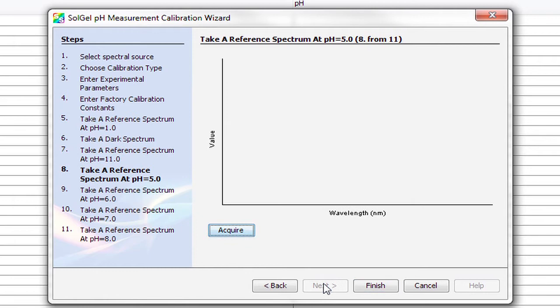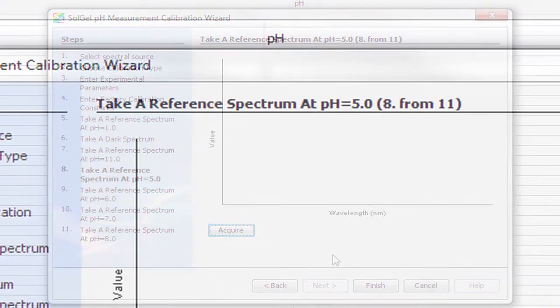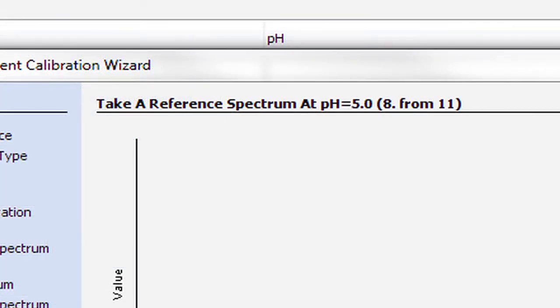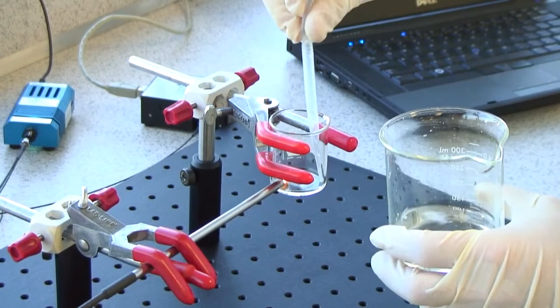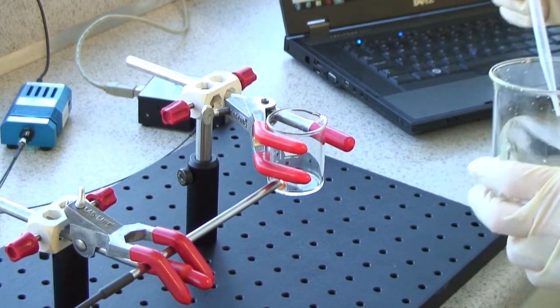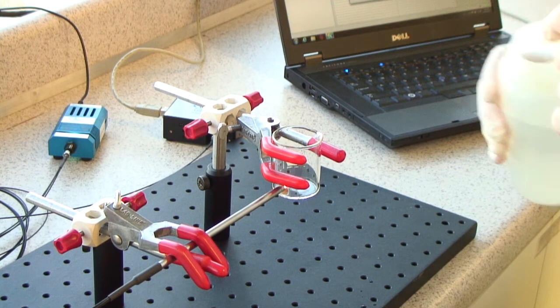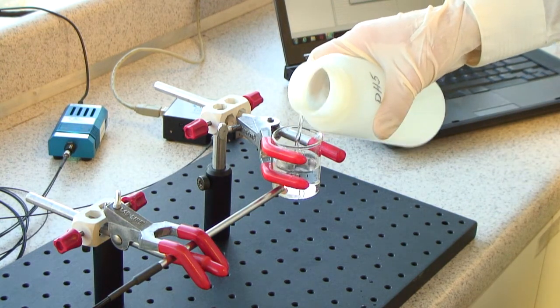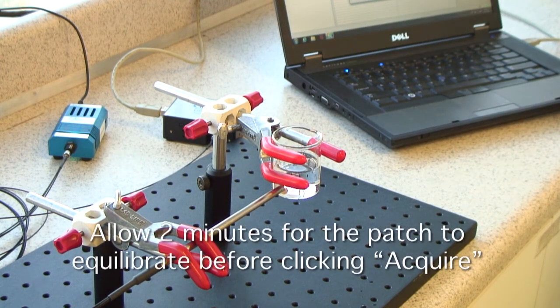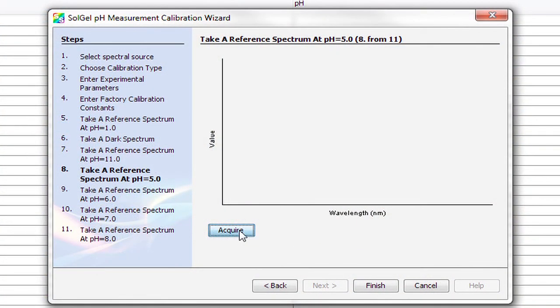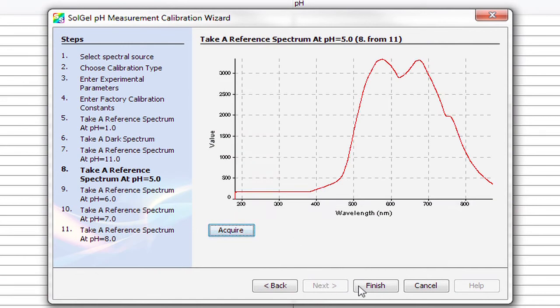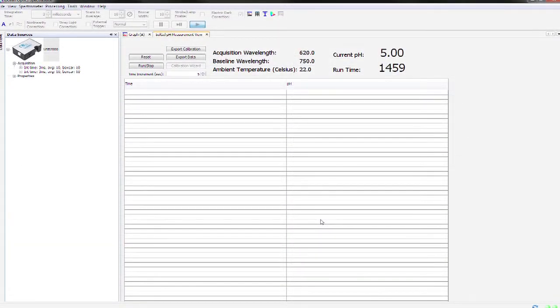Depending on the pH value you entered, the system will either ask for pH 5 or pH 8 buffer. In this case, it asks for pH 5, and, similar to the last buffer change, we'll remove the pH 11 with a pipette, replace with pH 5, and rinse once more to prevent contamination. Again, allow 2 to 3 minutes to equilibrate. Once a sufficient amount of time has passed, click Acquire and then click Finish. You're now ready to take pH measurements and to use the other features of the pH module.